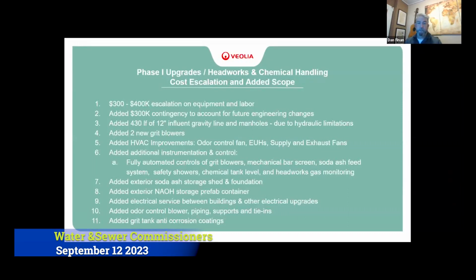A number of controls were fully automated and brought back to the plant, able to run through SCADA in the control room. And you can see from the list here, instead of having the soda ash feeder in the chemical room with worries about the slurry line getting clogged, we moved it outside to the grit chamber.